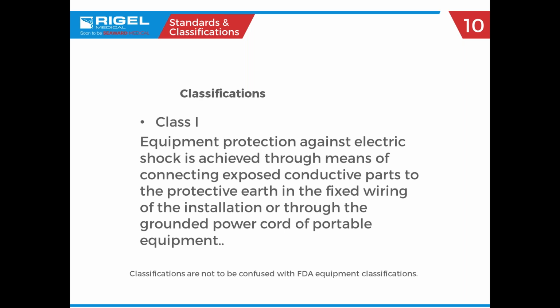That ground pin is what we really count on to attract any of that leakage current back to ground. So if you look at the back of a medical device, I'm sure you all know this, there's a symbol telling you which class of device it is. The circle you see that just popped up with the ground pin inside of it - that is your class 1 device.